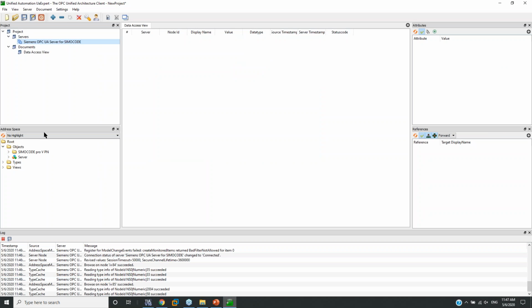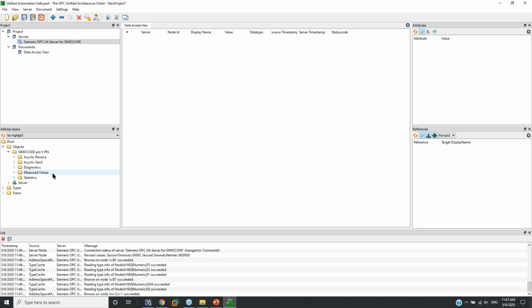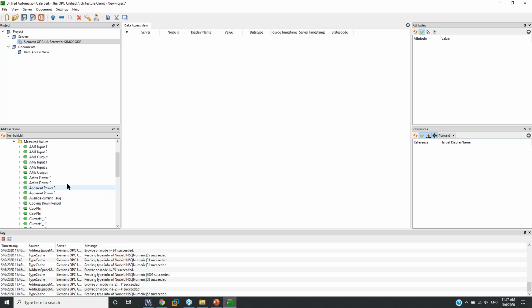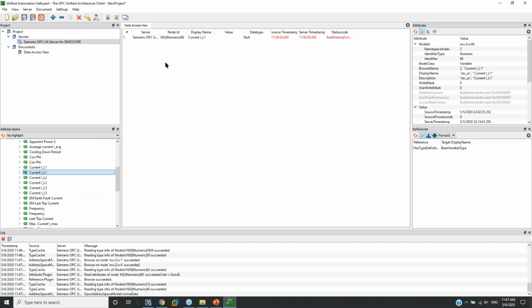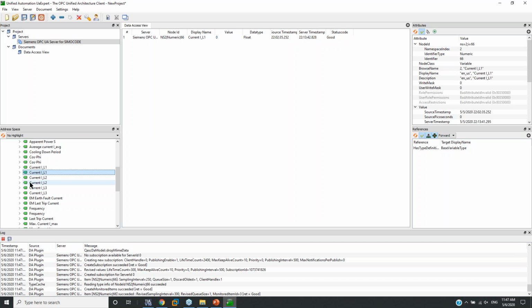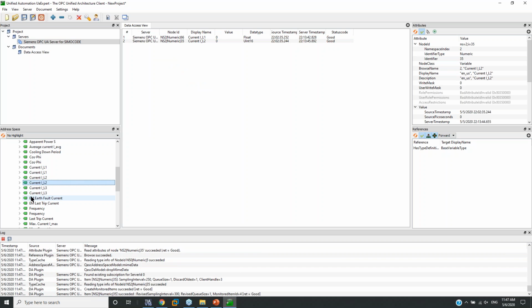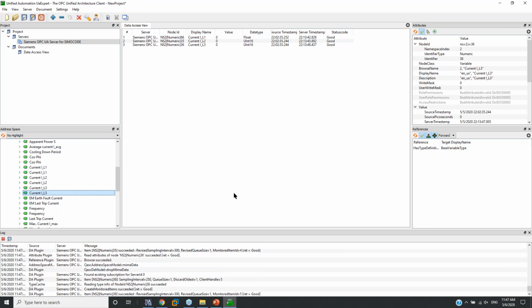I come back to this software and now I can grab any tag I wanted. So let's go measured values. And notice I didn't create any tags to populate this. This is automatically done with OPCUA. So I'm grabbing currents, dropping that down. Notice that I grabbed a float, which is going to give me actual current readings, and then the other two are going to give me percentage.